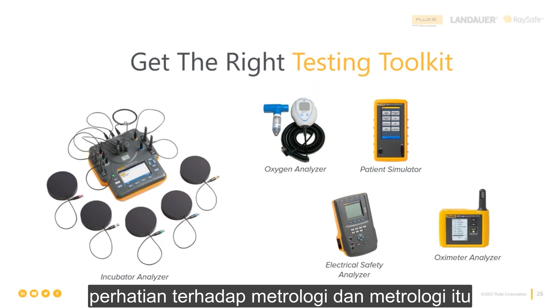Yeah, so here I would like to discuss the importance of choosing the test equipment that will be right for you and answer the needs that you have when testing the incubator and the environment around it, and the equipment that you can rely on for doing the right job for you. So we're suggesting that you need to use separate equipment other than the self-test function, because as specified by regulatory bodies such as the FDA, independent objective evidence is required. So when choosing your instrument, one thing that we would like to advise here is that you need to pay attention to metrology, and metrology matters.